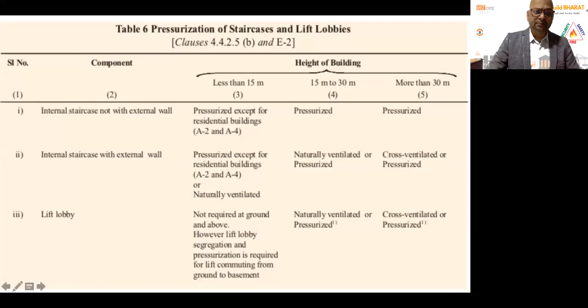But before we end, I will leave these questions for you to think over and look at your facility: What is my fire protection strategy? Do I include fire smoke management in that strategy, or is it limited to only active systems? What are my smoke controls? Is it adequate? I've been given only one exhaust fan, but is that really adequate to take the smoke out? What is the CFM, and what is the location of that exhaust fan?